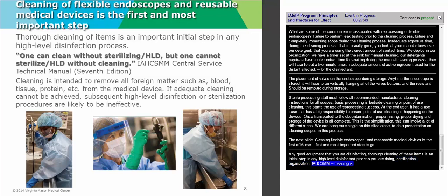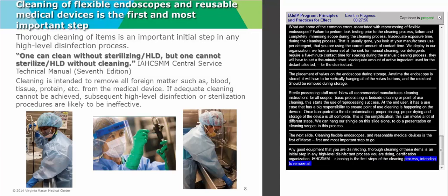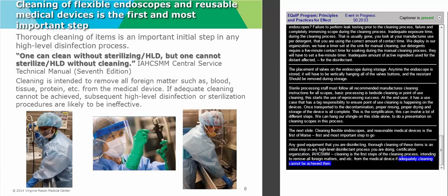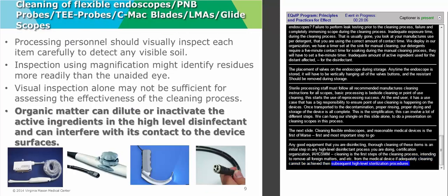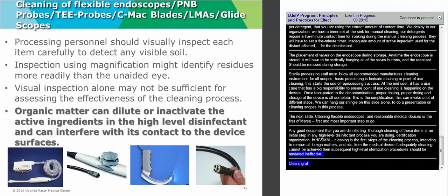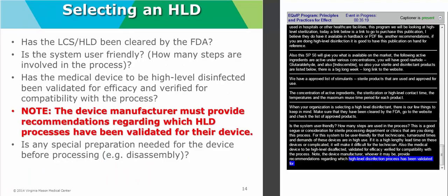Cleaning is intended to remove all foreign matter, such as blood, tissue, protein, etc., from the medical device. If adequate cleaning cannot be achieved, then subsequent high-level disinfection or sterilization procedures are likely to be rendered ineffective. Cleaning of flexible endoscopes, again, PNB probes, TEE probes, C-MAC blades, LMAs, glidoscopes, the list goes on to what our technicians get a hold of and process. But processing personnel should visually inspect each of the items carefully to detect any visible soil. So after the manual cleaning process, that visual inspection is important to ensure that any gross bioburden that is left on is found, and if it is still on the device, then the manual cleaning process should start again.